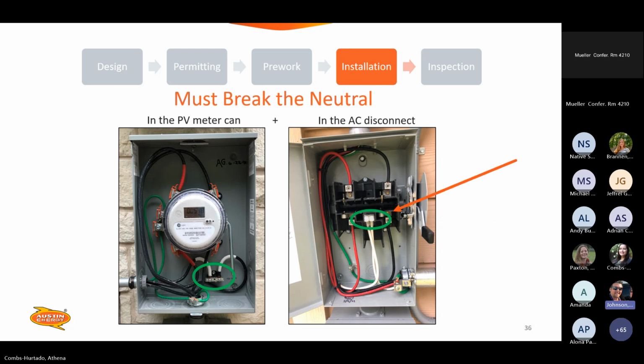Okay, in our design criteria and our interconnection guide, we cannot have a bond in the meter or the disconnect. So we need to have them isolated appropriately for testing purposes. You can use a Polaris or a terminal bar as shown on the left there, but we want to verify, and for your technicians to verify, that there's no bond being made inside the meter can. Next slide, please.